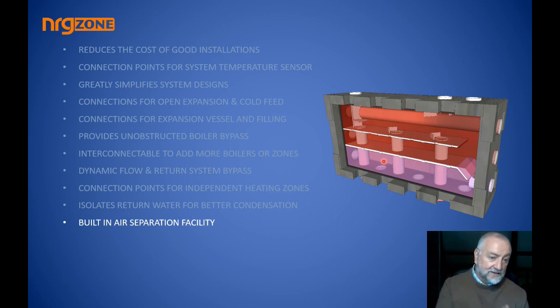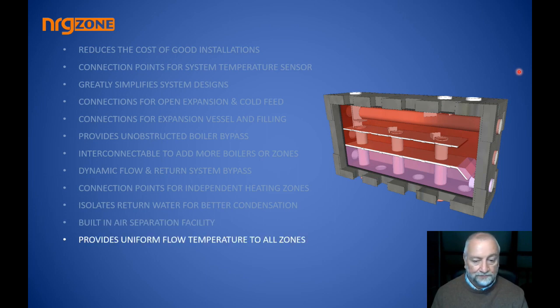Every single time the water passes through this manifold, it's being deaerated in an extraordinary way with elongated chambers catching every tiny microbubble and forcing it up, allowing it to drift to the top. Certainly when the system stops, any air trapped in those spaces will migrate to the top, and even as it's operating, the air is being directed towards the air trap. So uniform temperature to all circuits, we're back at square one.